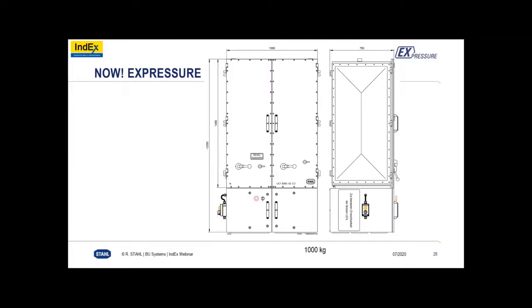did a new engineering together with the customer, and now we were successful in placing everything inside of one of our big ExPressure cabinets, size 62, with a connection chamber under it, and thus we achieved a footprint saving of 45% and a weight reduction of 42%. So they have much more space in the control cabinet of the crane, and there is more space also for other installations from the customer, and also better routes for the drivers themselves. So the overall weight went from 1,700 kilograms between those two enclosures down to 1,000 overall. So a significant space and weight saving.